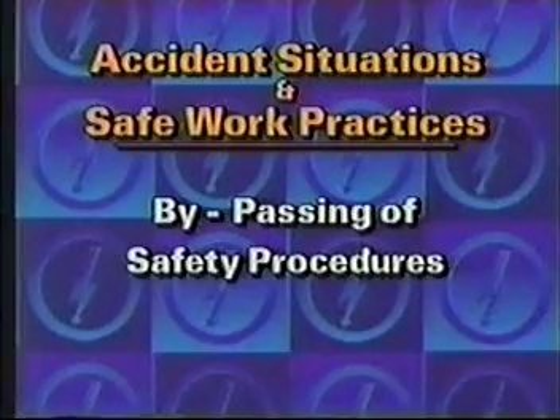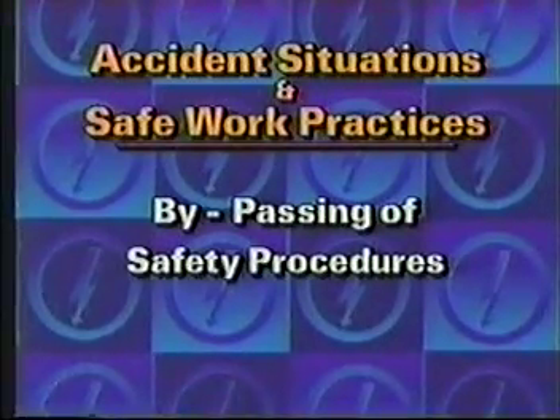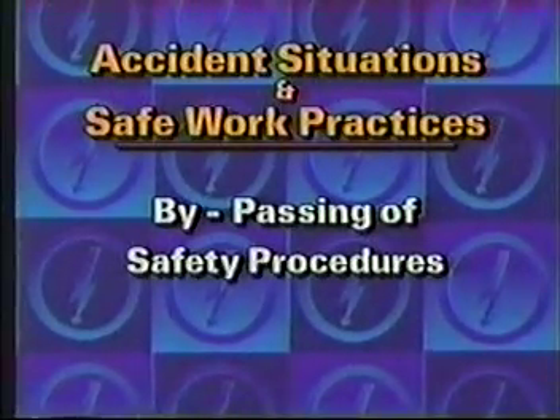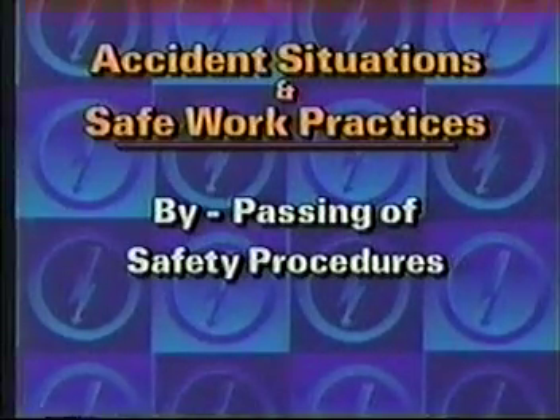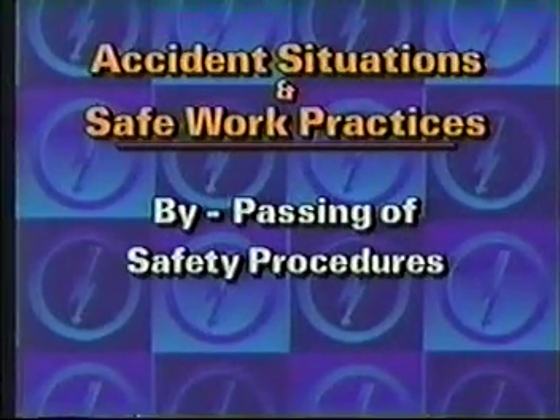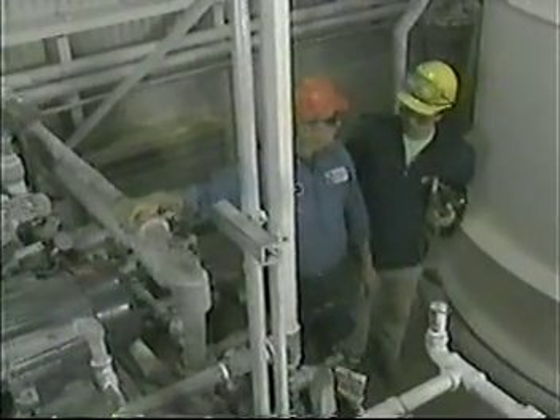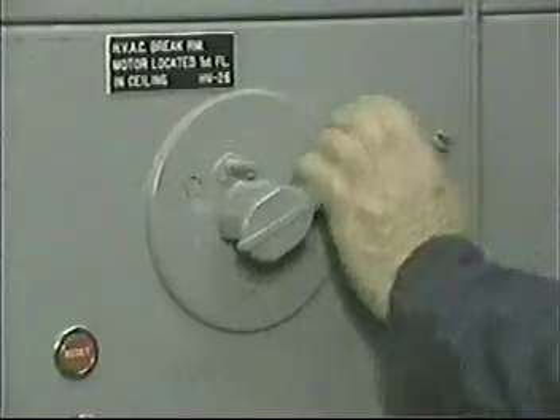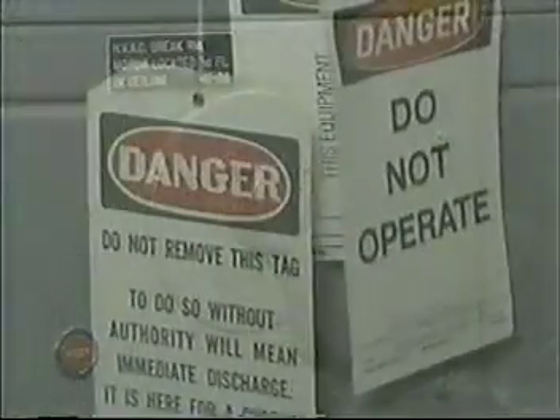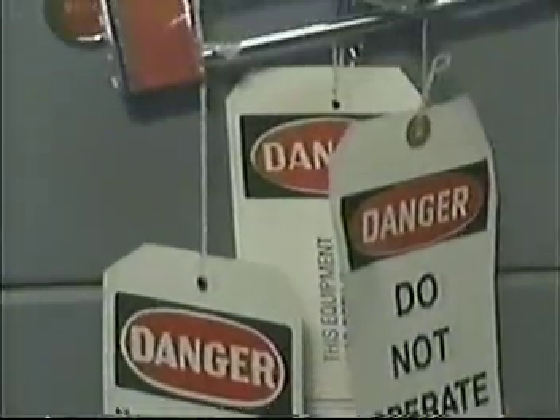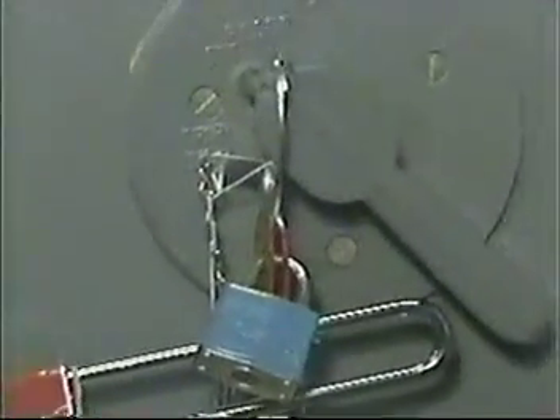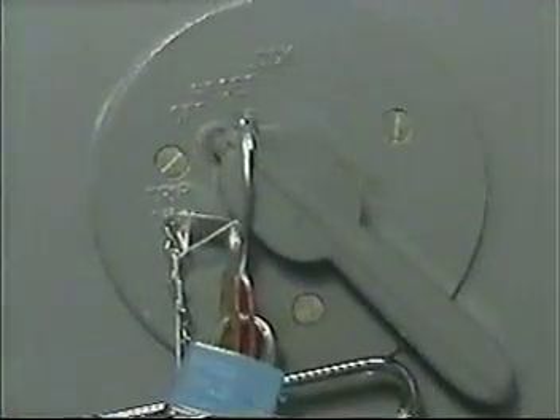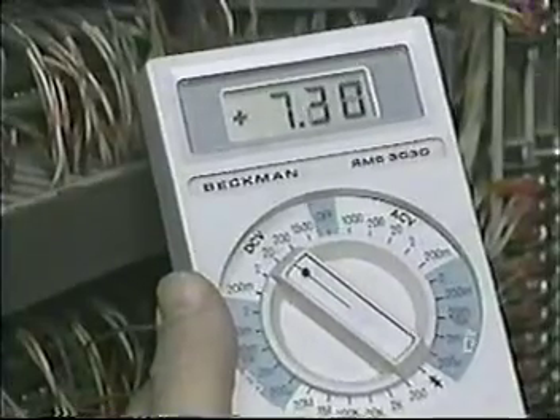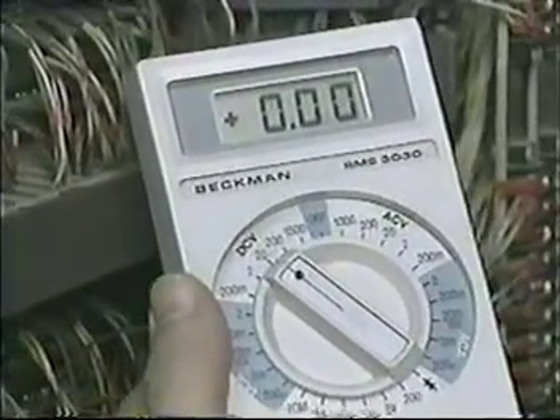The fourth and final category is unsafe situations that occur when safety procedures are ignored or intentionally bypassed. For example, working on equipment that has not been correctly de-energized, locked, and tagged out. The rule to follow here is de-energize and lock out every time. Don't work on electrical equipment unless every source of energy has been neutralized, locked out to prevent inadvertent startup, and tested to ensure that the de-energizing process has been completely effective.